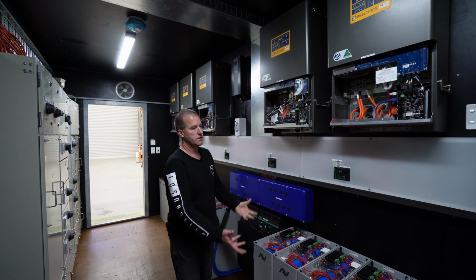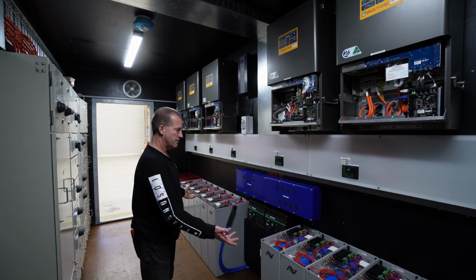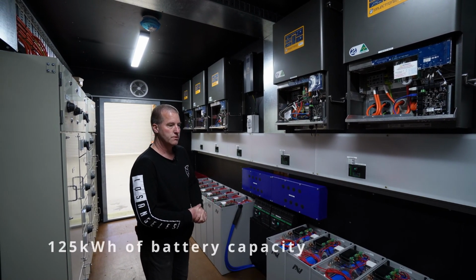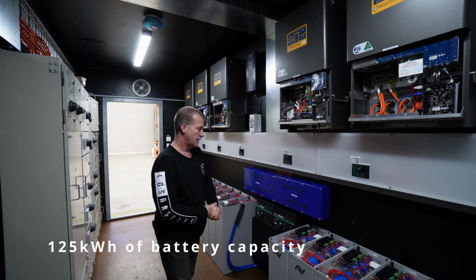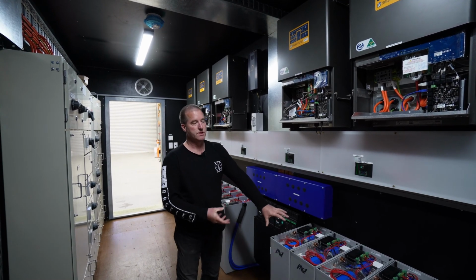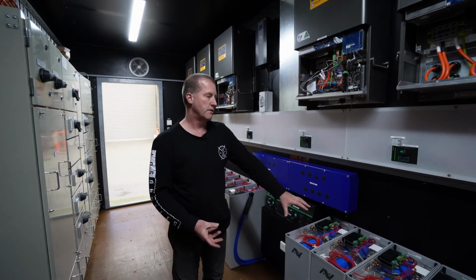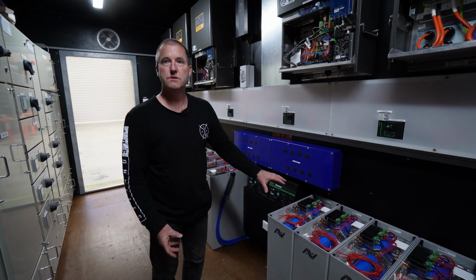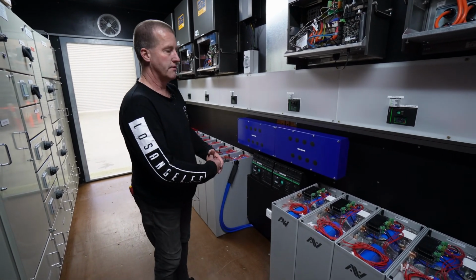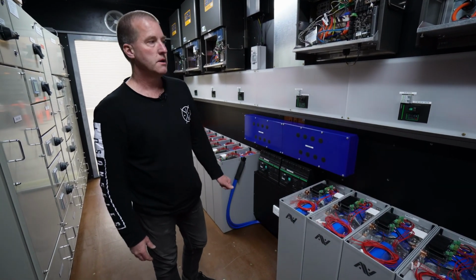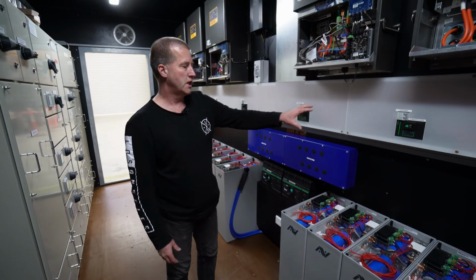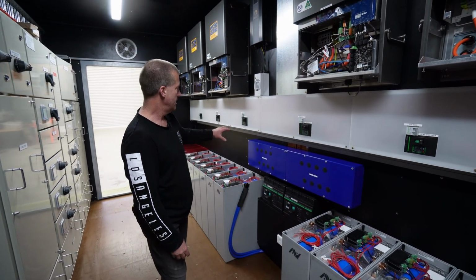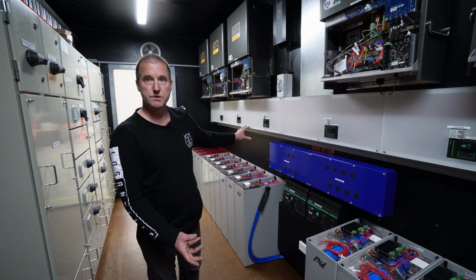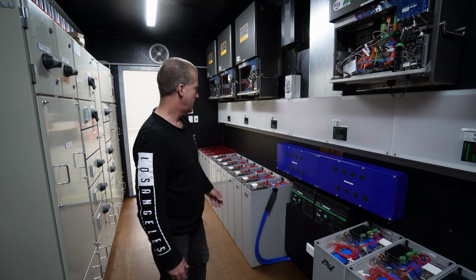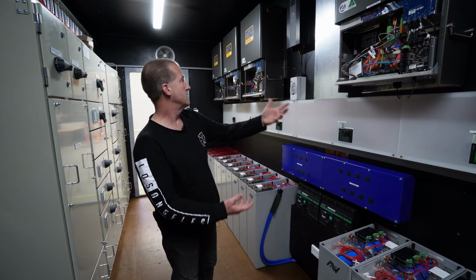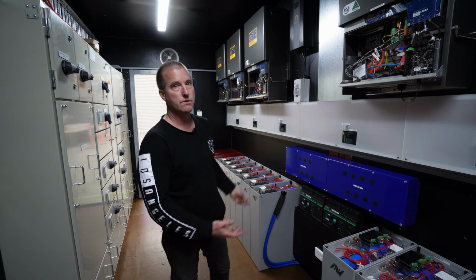So the energy storage system can fill up - in this case we've got 125 kilowatt hours of storage, and the ability to charge this battery as fast as we want. It can charge in around 20 minutes based on the size of the fuses, giving us an enormous amount of peak power. We can be charging from the grid, solar, and the generator all at the same time if we want, or any of those feeds, and producing 2 phases or 3 phases or both all at once.